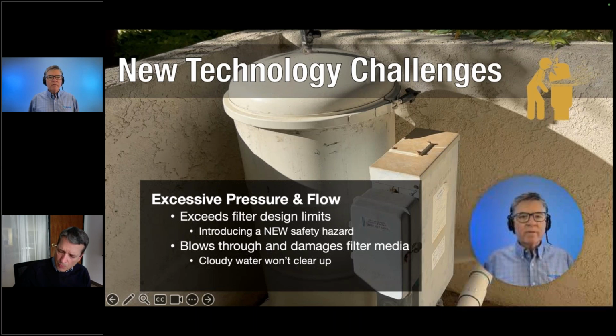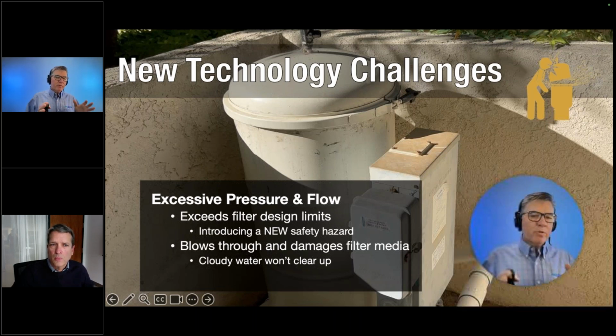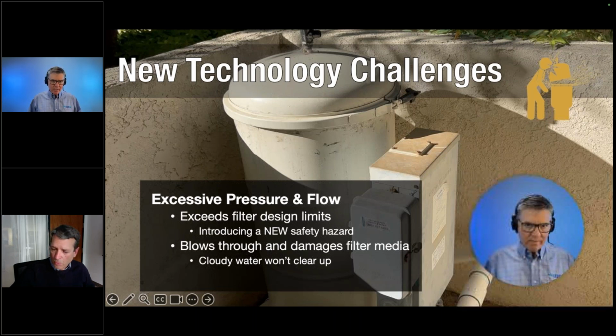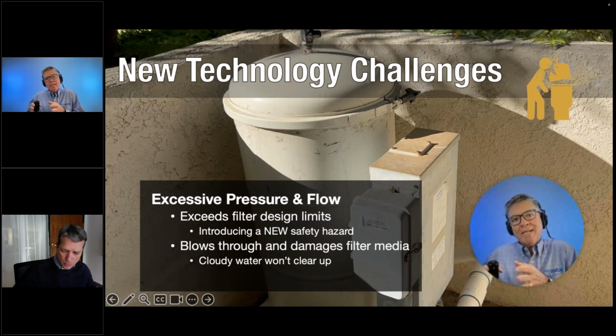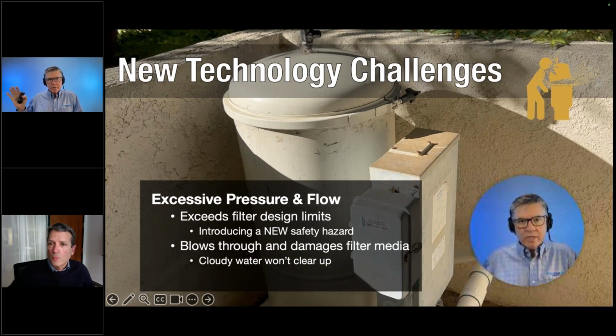And so that's one of the gotchas that we've seen in doing the variable speed replacements in San Antonio. We had 3 different pools where the filters, I got to be careful because I've used the city name, but there were 2 filters that were never sized right in the first place. There should have been 2 and they only installed 1. And what was happening is these new variable speed pumps were actually achieving, because we installed brand new flow meters on everything that actually controlled the drives, flow rates that these pools had never seen historically.